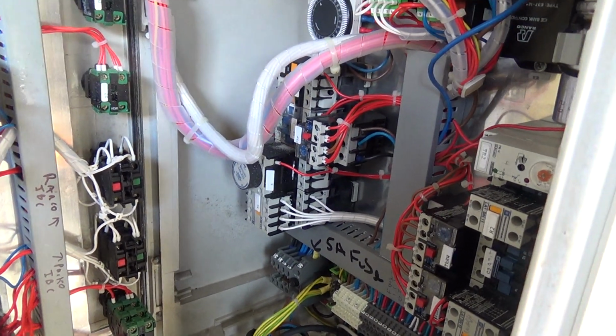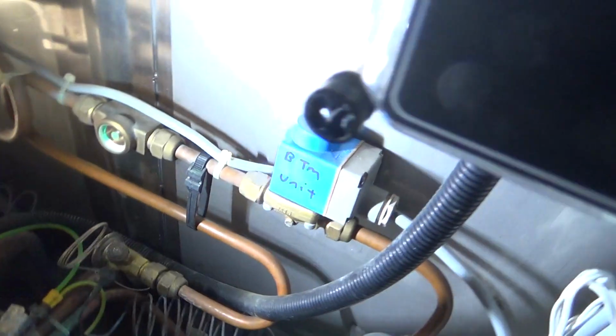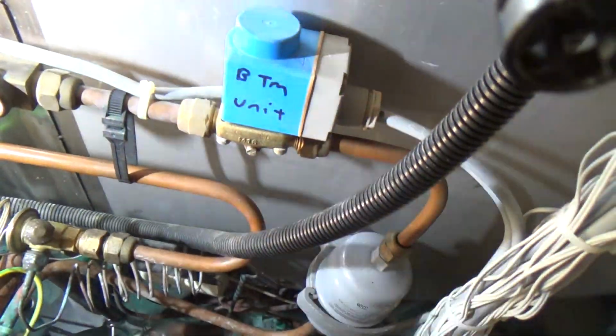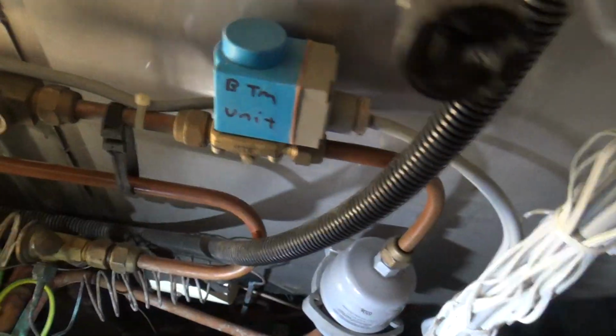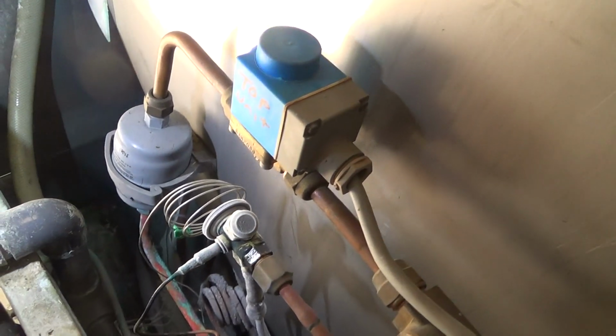But then we had noticed that one of the two units was turning off when it should have been on, and that was the one that's playing up, which is this solenoid valve here. Let's turn the light down a bit. So we've got two separate coils, two separate systems. This one was shutting off, and they're run off of these 3 ice bank sensors.